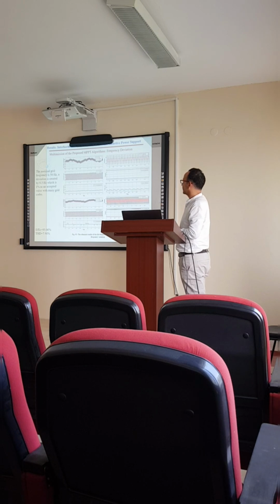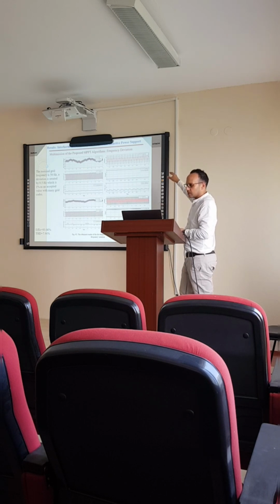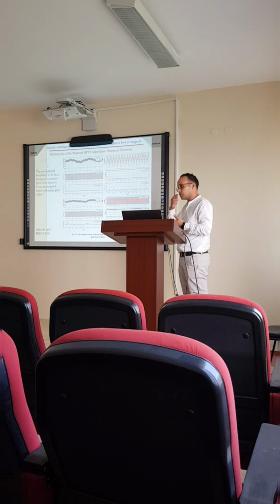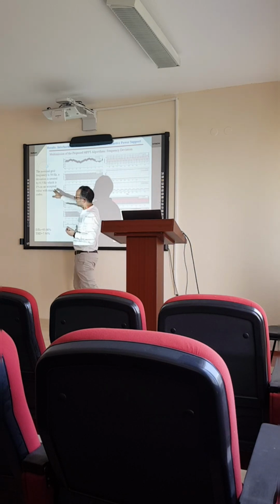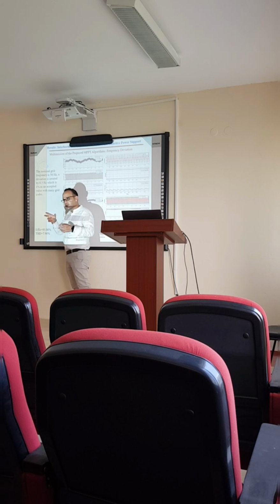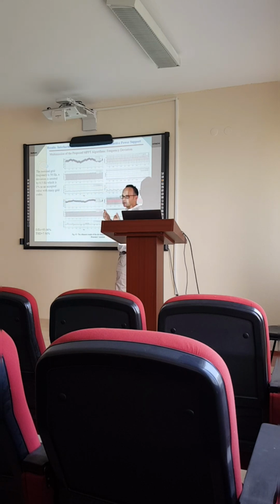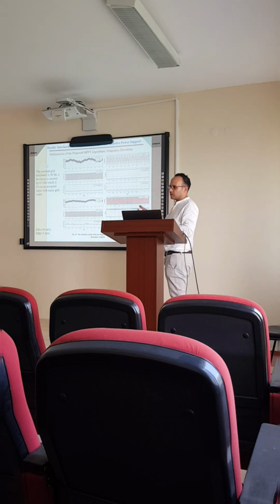Sure. And this is actually up to some level, doctor. Maybe the inverter will be done. So under this situation, we are checking the frequency sensitivity. We change the grid frequency by half hertz, which is 1%. I think it's acceptable in the code to change by half for a specific amount of time before disconnecting the inverter. Up to the code that I read from, 1% is somehow acceptable.